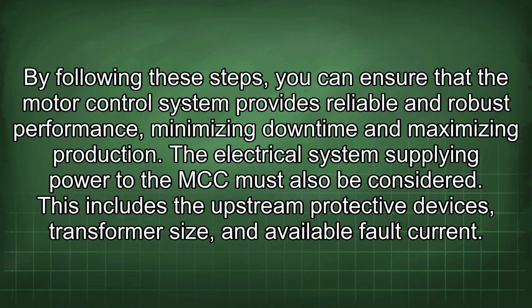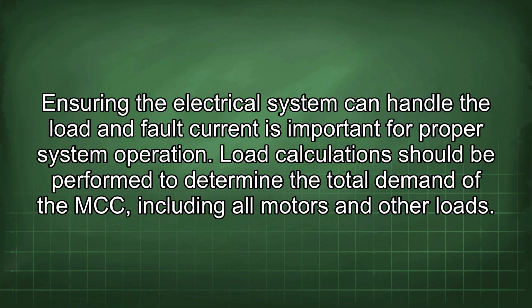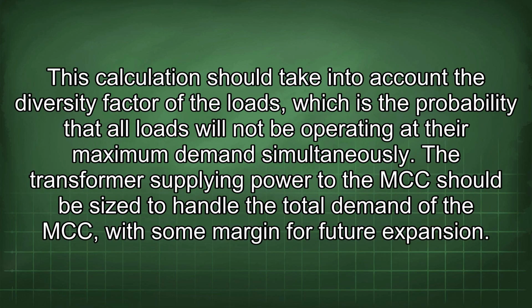The electrical system supplying power to the MCC must also be considered. This includes the upstream protective devices, transformer size, and available fault current. Ensuring the electrical system can handle the load and fault current is important for proper system operation. Load calculation should be performed to determine the total demand of the MCC, including all motors and other loads. This calculation should take into account the diversity factor of the loads, which is the probability that all loads will not be operating at their maximum demand simultaneously.